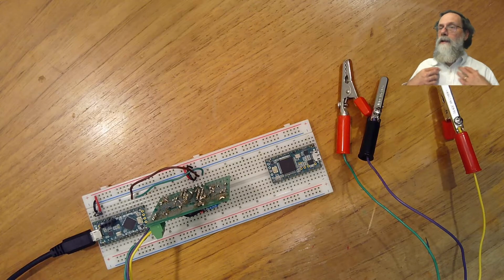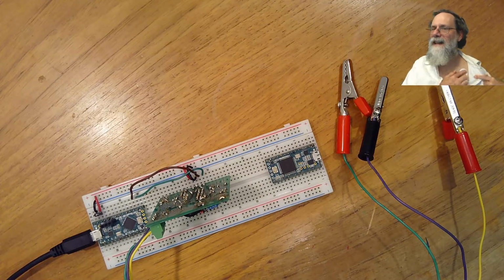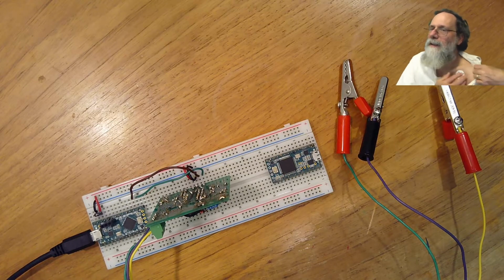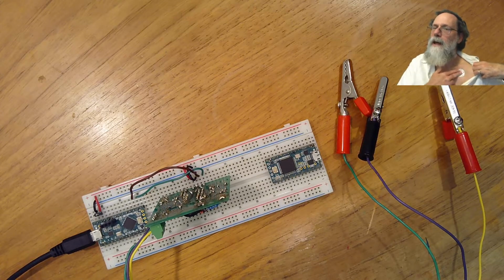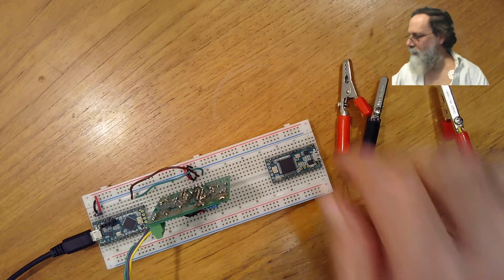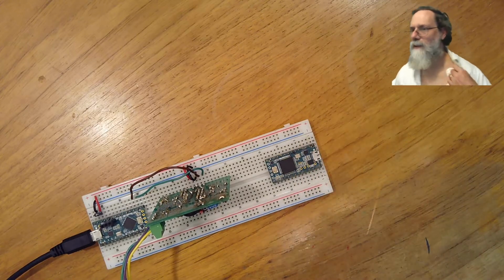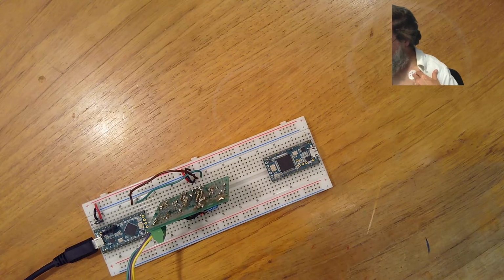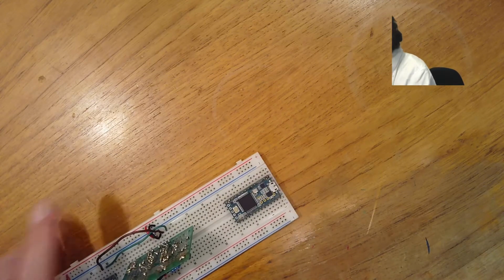And so the electrodes, instead of being put on the wrists or ankles, are put just under the collarbone. And if you take a look, collarbone here, and there's a spot under the collarbone where there isn't really any muscle. There's muscle further down. You don't want to really run onto that. So you just put it under the collarbone where there isn't much muscle. And so I am now going to try to hook these things up. And if I can remember my color code here, I better check. I had the yellow was the right one and the green was the left one.